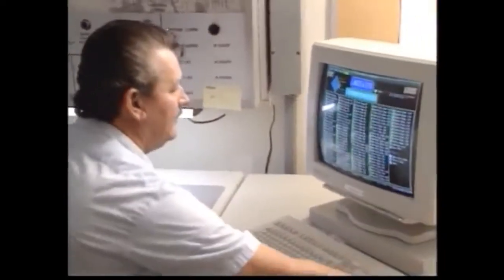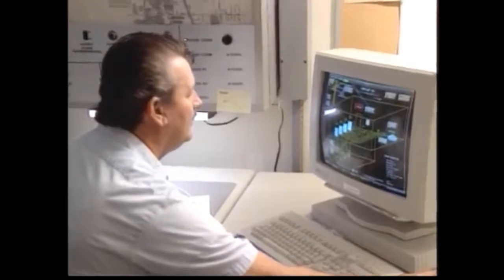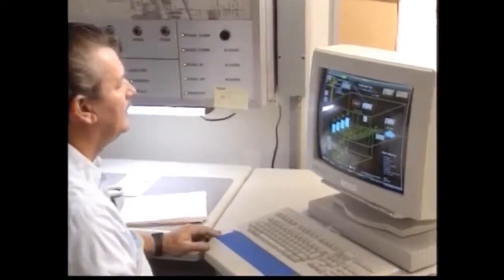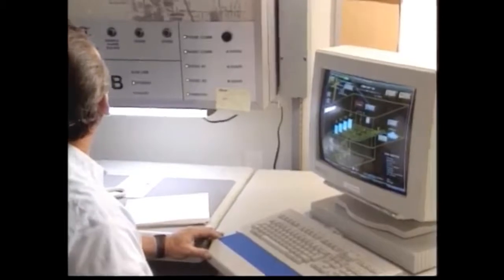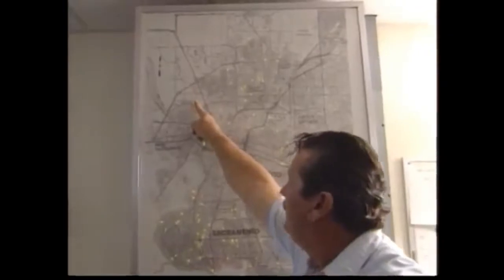Not every agency can afford to use the kind of telemetry systems that specify the item of equipment and the problem in a remote lift station. However, many agencies use alarm systems simply to indicate that the lift station needs to be visited. The signal is received at a facility that is staffed 24 hours a day. In many cities, this is the local police department or emergency dispatch center. When the station has a failure, the alarm is transmitted, usually through leased phone lines, to a control panel at the center. An indicator light for the particular station goes on when a problem develops, and a horn or some other type of noisy alarm may also be activated.